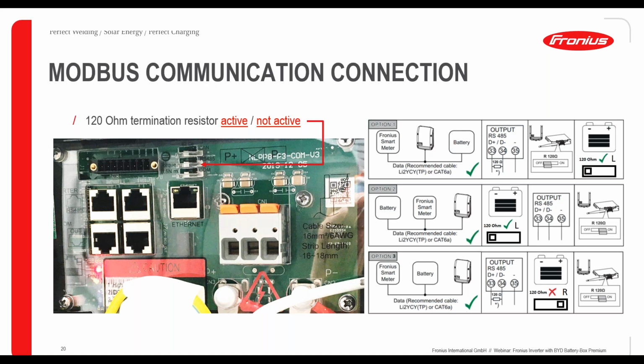After that, all you need to do is to determine the connection, so to set your termination resistor. Of course, with our Modbus connection, it is always necessary to use a 120 ohm termination resistor. And in this case, with the BYD battery box, it is possible to activate or deactivate the 120 ohm termination resistor on the battery system itself. So here you see on the left side the communication paths, and on the right hand side you see the dip switches that can be activated or deactivated. Depending on the position of the battery box in this Ethernet communication, you have to activate or deactivate the 120 ohm termination resistance. So we then have three options that you can see on the right hand side.